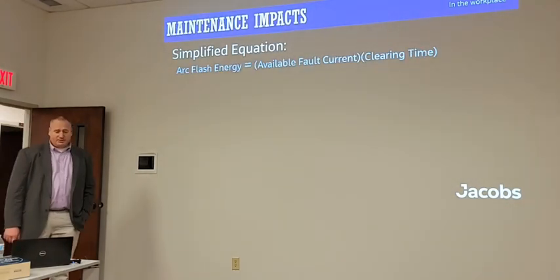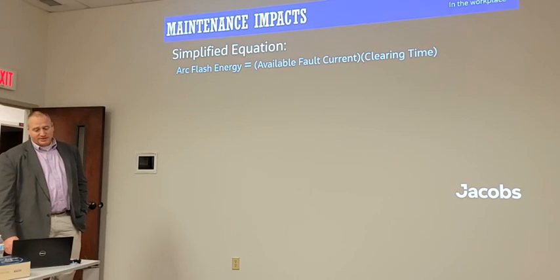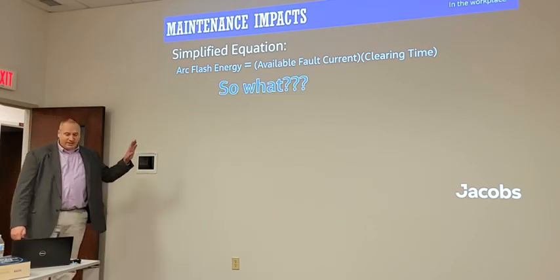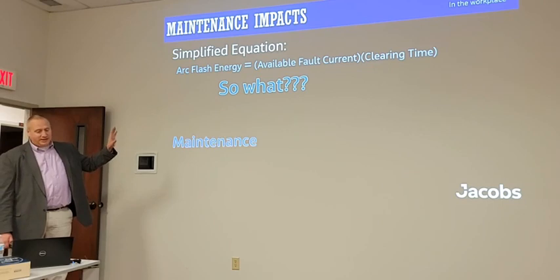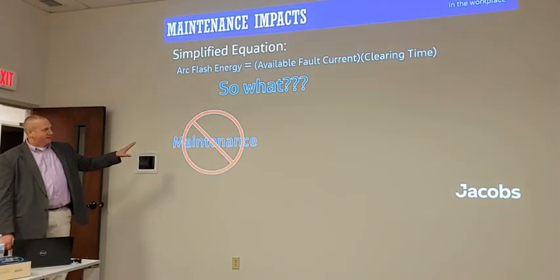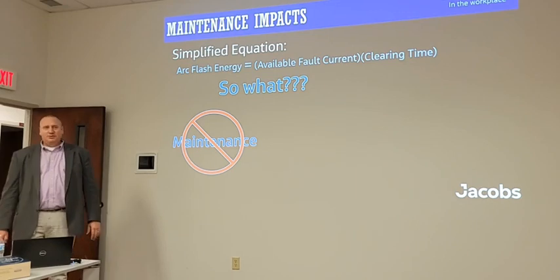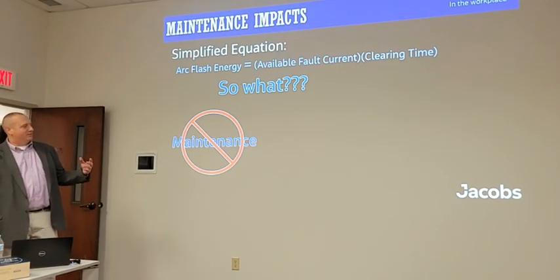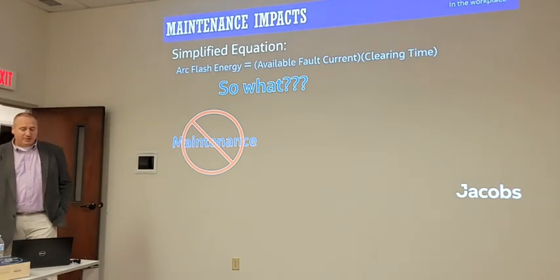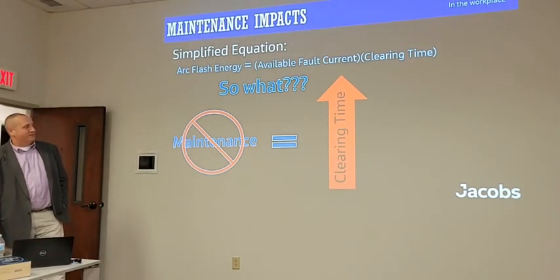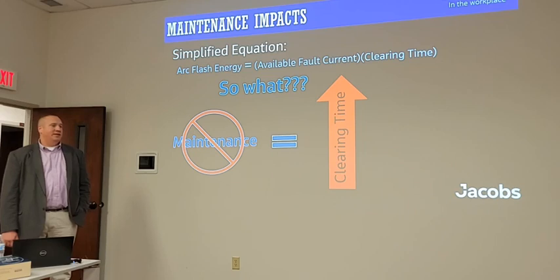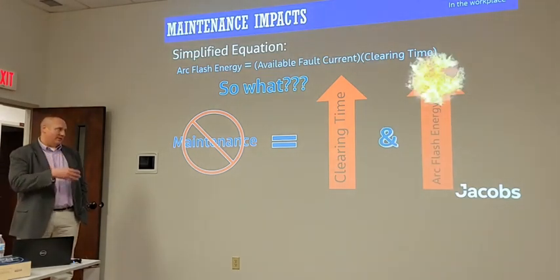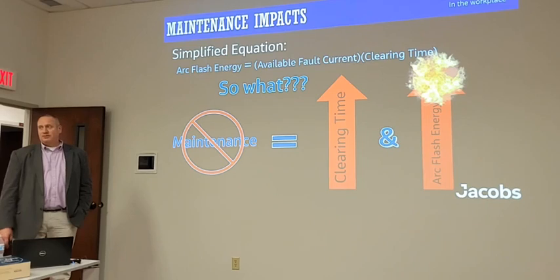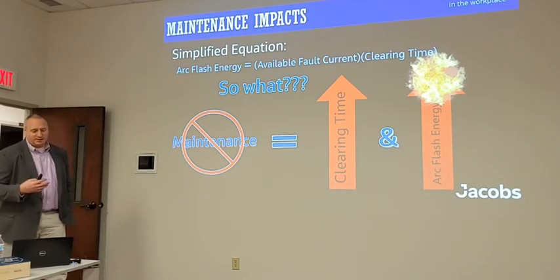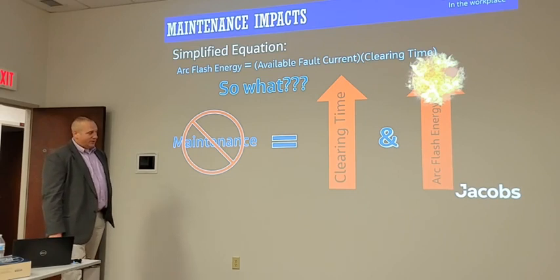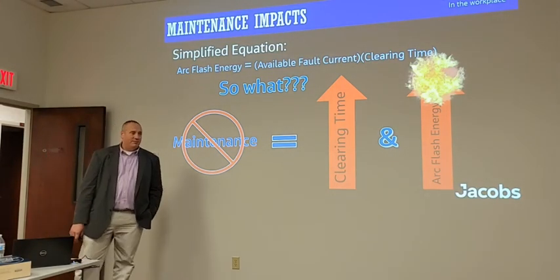The other issue that is very true in the real world is if you take into consideration the available fault current and the clearing time, and you look at maintenance. In a lot of cases there are a lot of facilities that don't do corrective maintenance or preventive maintenance or predictive maintenance on their low voltage equipment, 480 volt equipment, well then that's going to often increase your clearing time. And if it increases your clearing time, it's always going to increase your arc flash energy. So it is important to maintain your equipment, particularly any of the 480 volt protective devices that have mechanical movements.